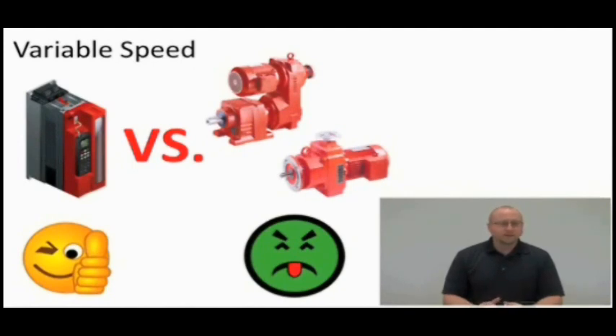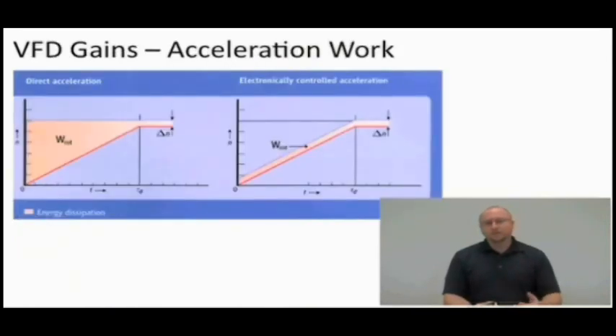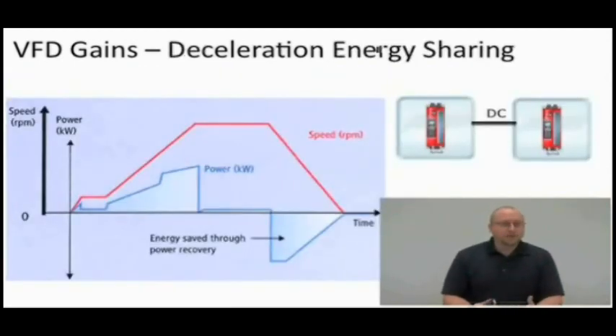Some other things that a VFD can do, some advantages it can give you, is when you're ramping up to speed. When you turn on a motor that's directly powered from the AC line, it comes up to speed, not instantly, and there's a lot of work being done in the rotor. When you use an inverter, you can control that ramp and the amount of work that's being done in the rotor, and that's some energy that you can save. You can also save some energy on the deceleration side when you're stopping the load. You may have heard of regenerative energy. A motor and a generator are very similar in their construction, and actually when you decelerate an AC induction motor, it acts like a generator, and it pumps energy back into the variable frequency drive. Now what you do with that energy, that's up to you.